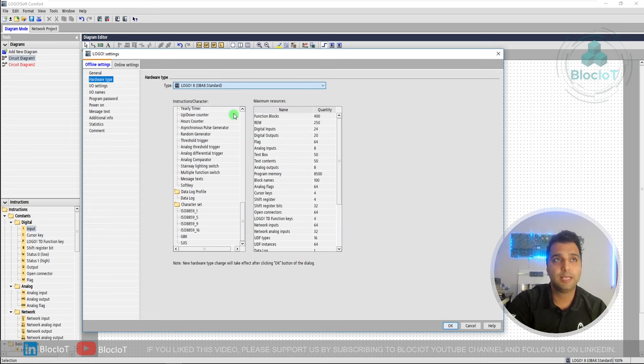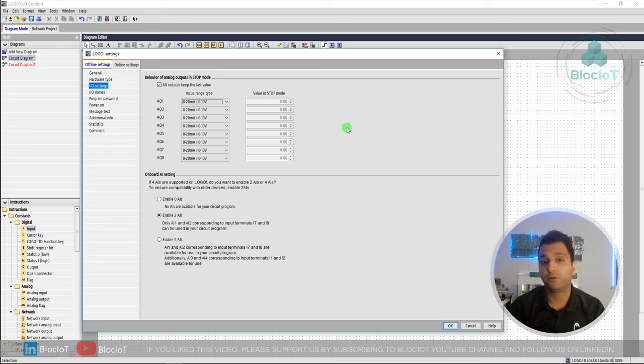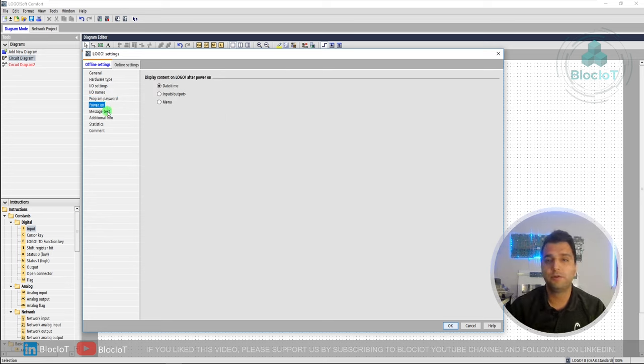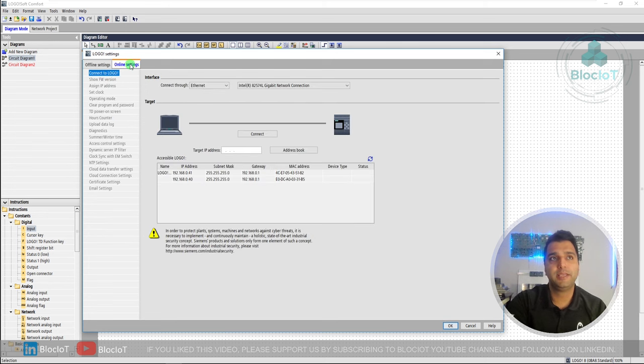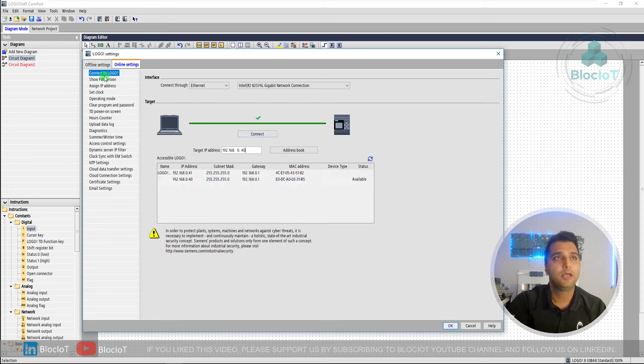Offline settings can be changed without connecting to your physical Logo, and when you download your project all these settings will be transferred. For example, you can define the hardware type — I have a Logo 8, or you can select Logo 8.4. You can adjust different I/O settings such as analog inputs and outputs, set up a password for your program, and define what is shown on the display when the Logo powers on. The Online settings are more important but require you to be connected to your Logo — enter the IP address and hit Connect.